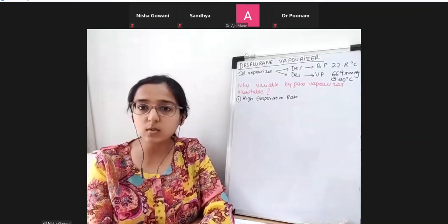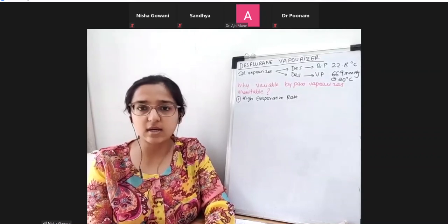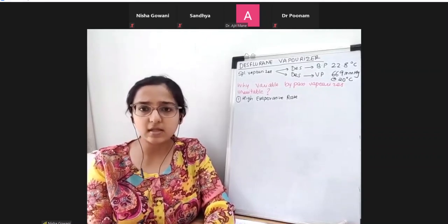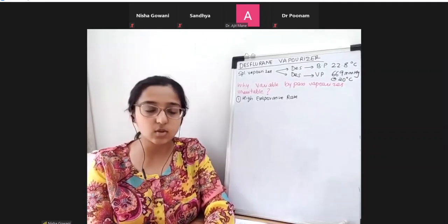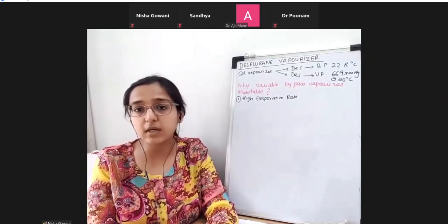Otherwise, we are using variable bypass vaporizer for all the other agents, right? Till now. But desflurane needs a specialized vaporizer. So why? Because desflurane has got certain different physical properties than other agents.